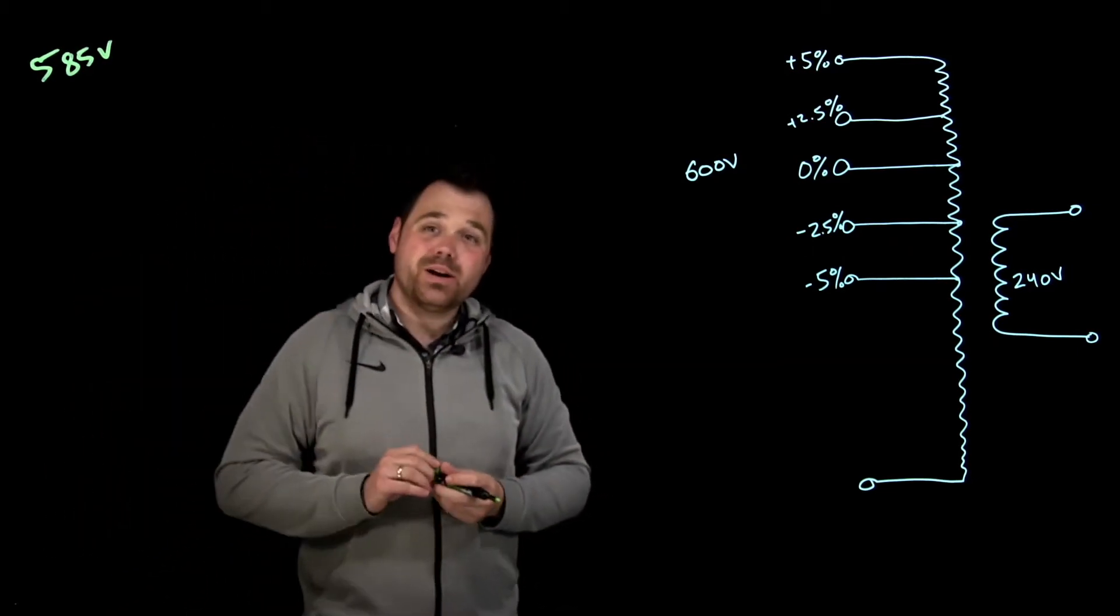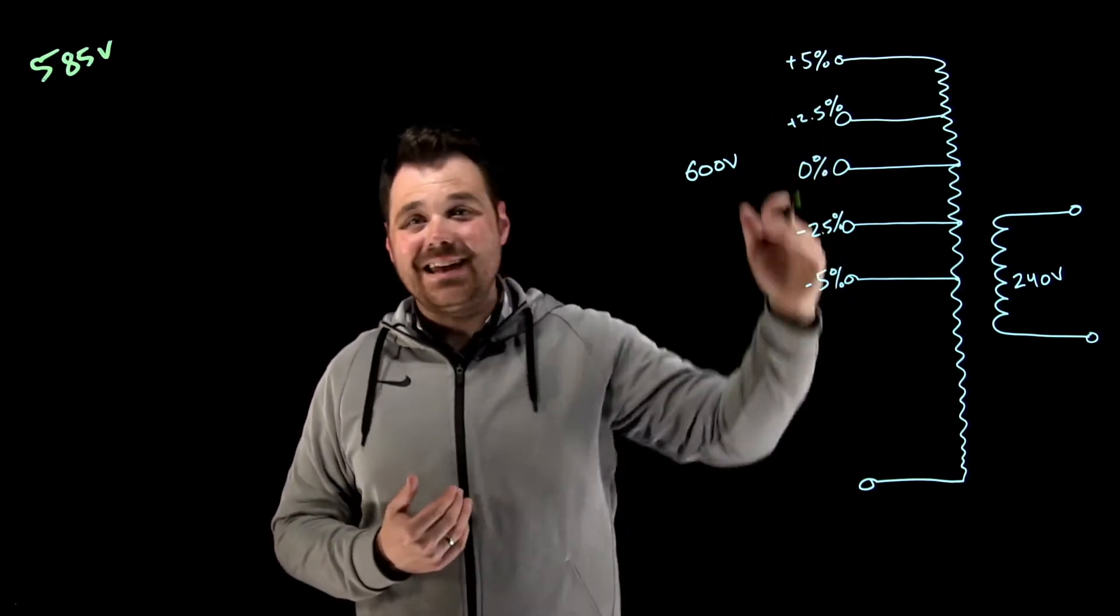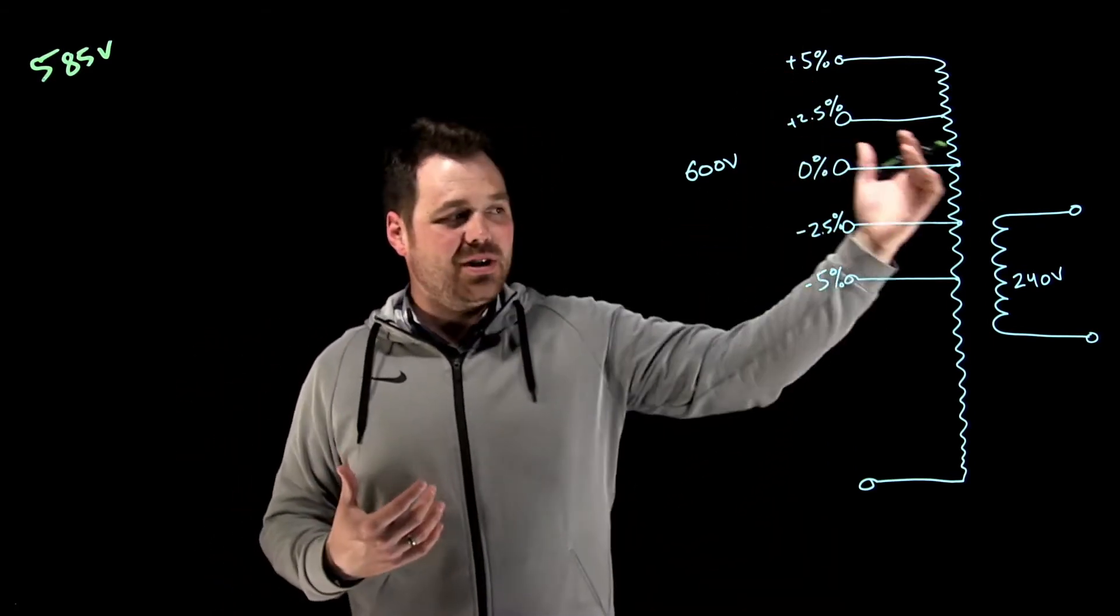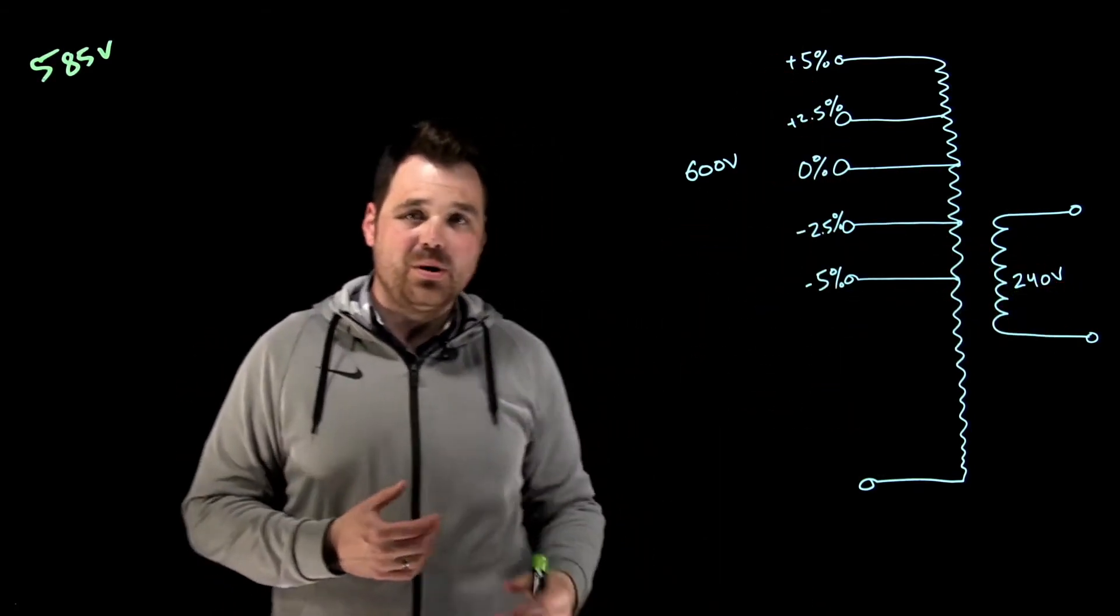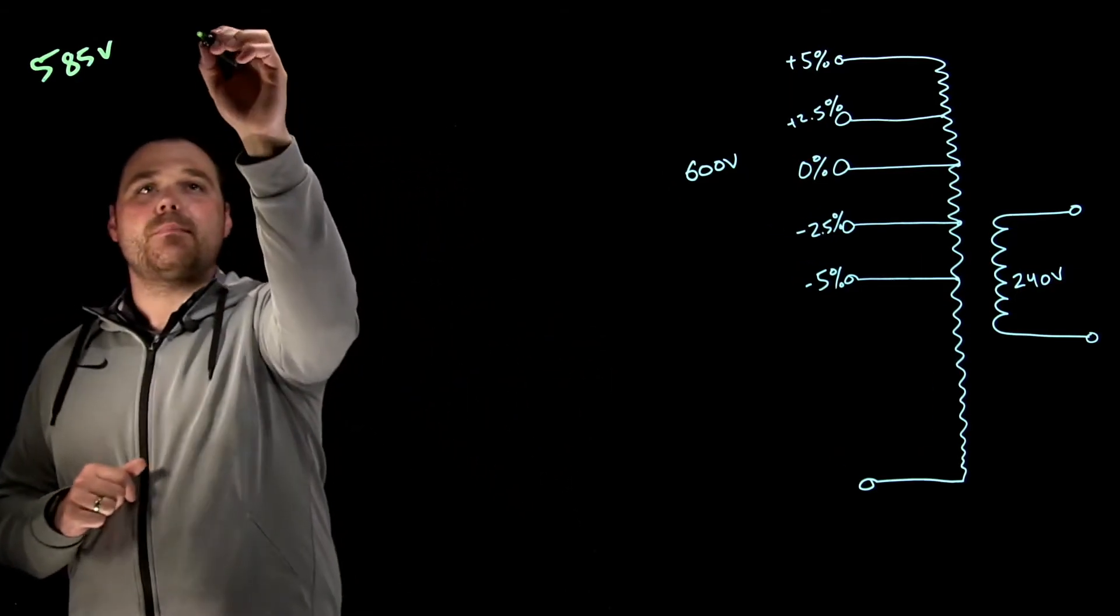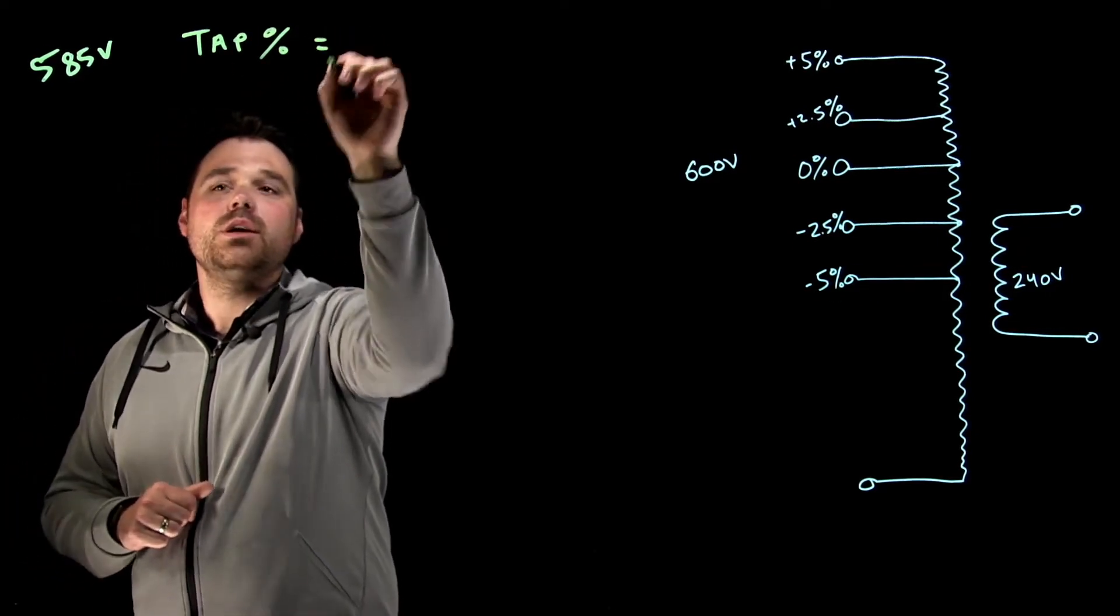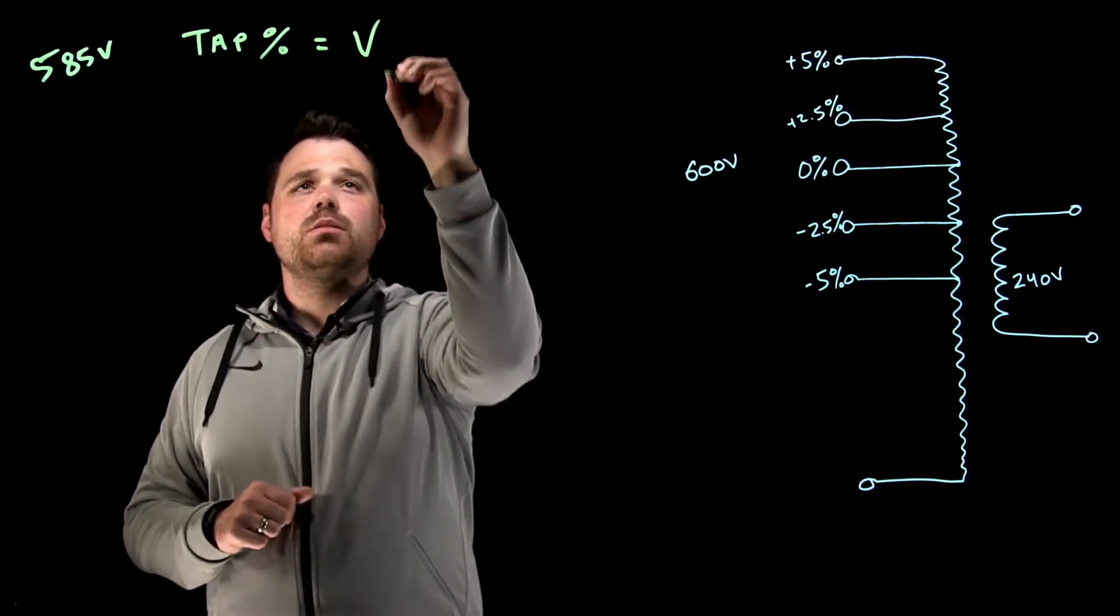So what we want to do is we want to calculate what tap setting am I going to use in order to get my rated 240 volt output. There's one formula we're going to use for this. It is the tap percentage equals the actual voltage minus the rated voltage divided by the rated voltage.